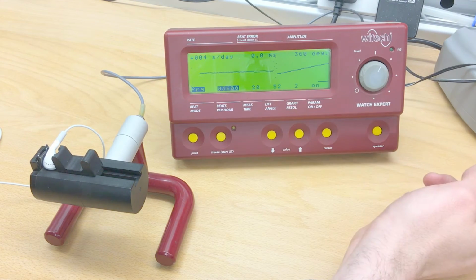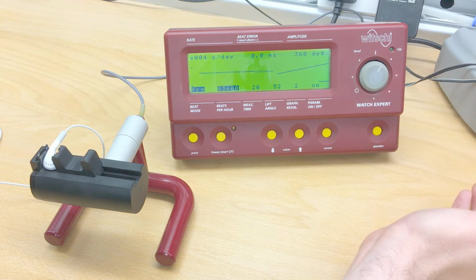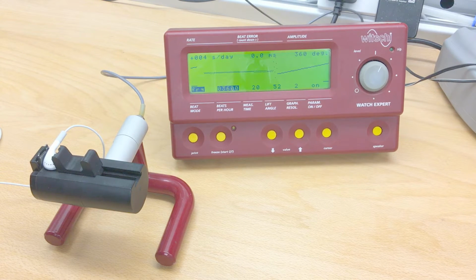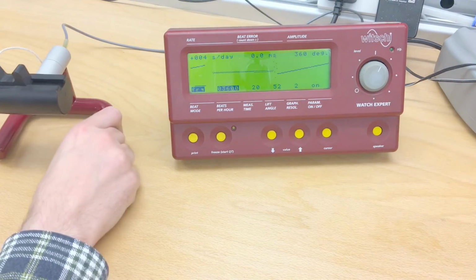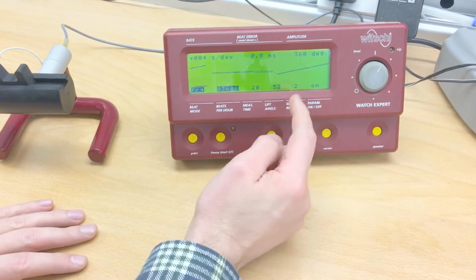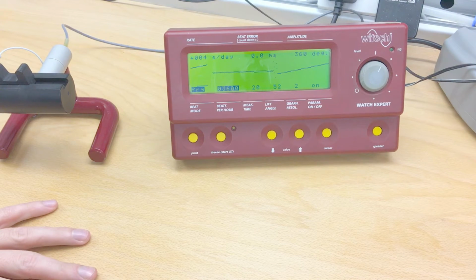So that's how I can assure you that the received pulse is accurate, quite aside from the fact that it is being output by a very high precision computer. If you think about the processor that drives that iPad and the number of crystals and resonators that serve as various time bases. Now, we have to open up the machine and adjust the trimmer capacitor that is expressly for the purpose of calibration.